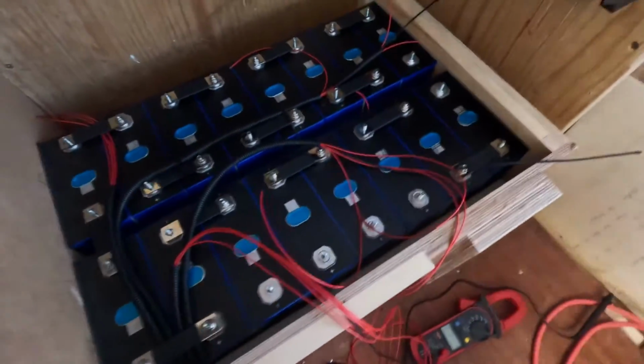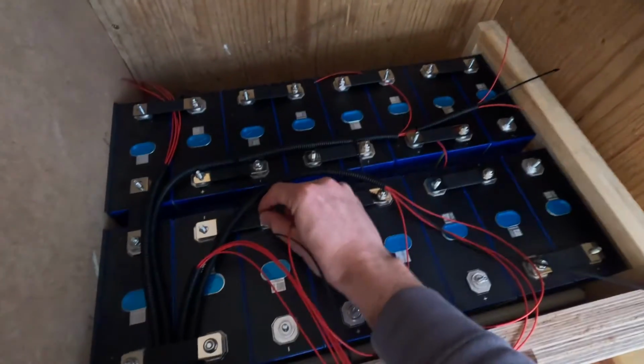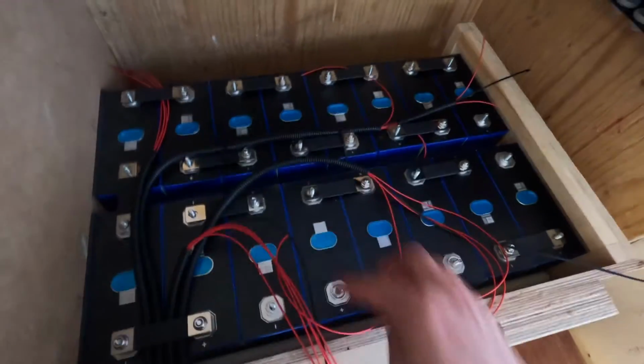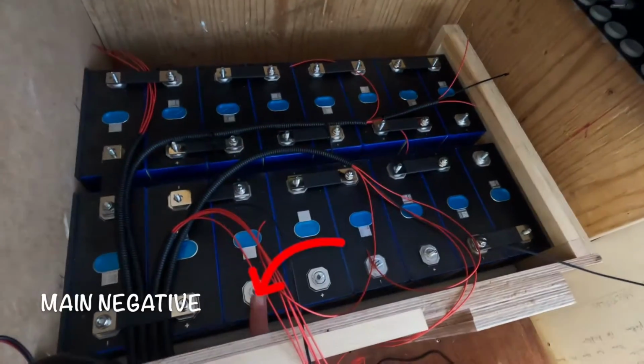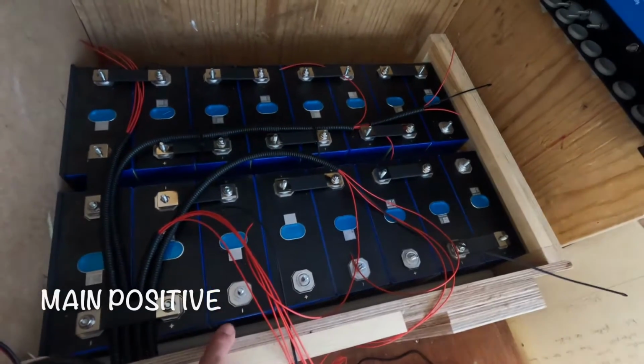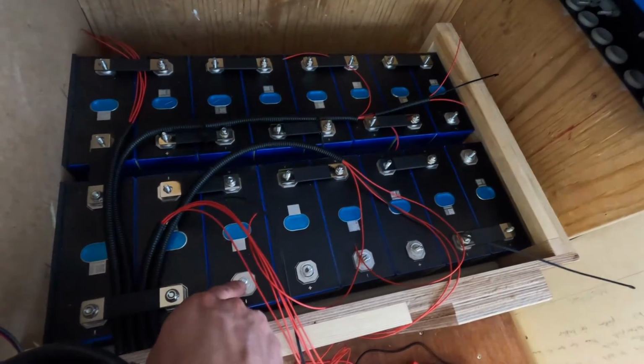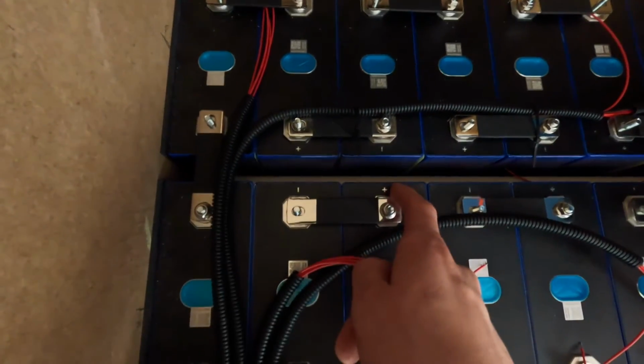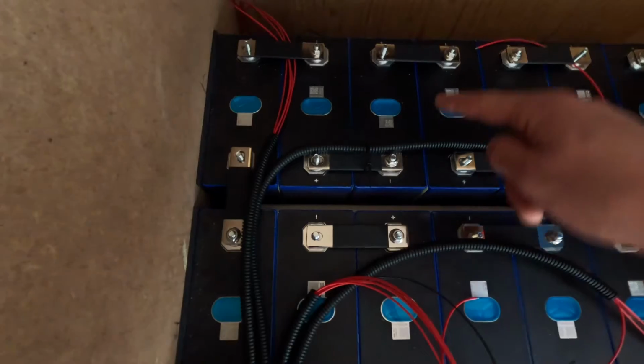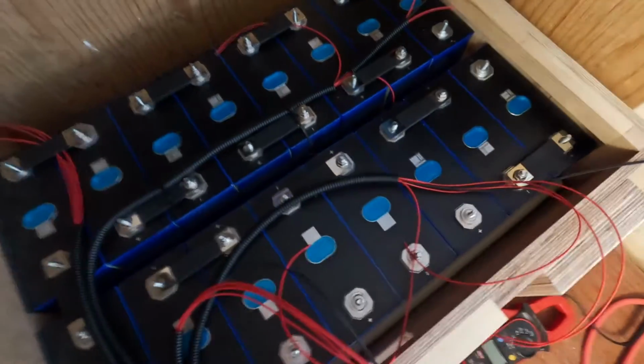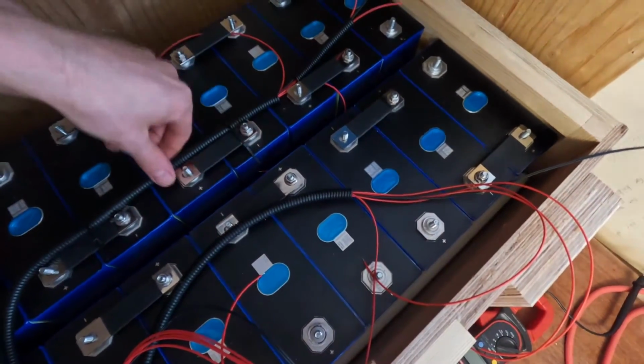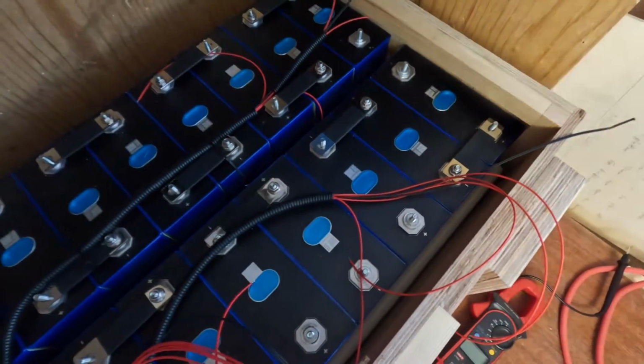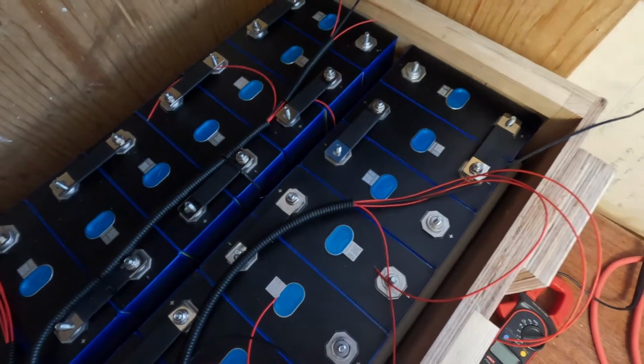So you have obviously a plus pole and a minus pole on each battery, and this will be our main negative, main positive, and then all these 16 cells will be connected in series. So you will go through the first one, connect to the next one, which then has the opposite sign. So this is the positive to this cell, and then your negative to this cell, and then you will just continue all the way around like this. I'm missing some bus bars here now, and I'm just having these wires to be able to keep the other wires in place while constructing that harness.